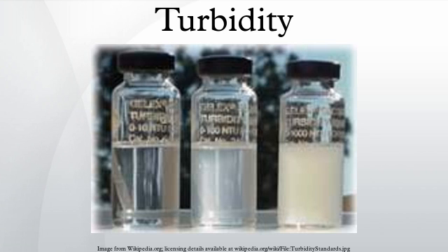Systems that use filtration other than the conventional or direct filtration must follow state limits, which must include turbidity at no time exceeding 5 NTU. Many drinking water utilities strive to achieve levels as low as 0.1 NTU.